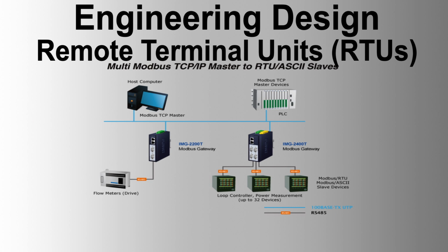3. Programming capabilities. It should be possible to program in ladder logic, text, as well as drag and drop function block formats and other formats supported by IEC 61131. Additionally, users should be able to enter program titles, comments, and I/O lists, and modify programs both offline and online, with changes stored permanently and not lost during an RTU reboot.